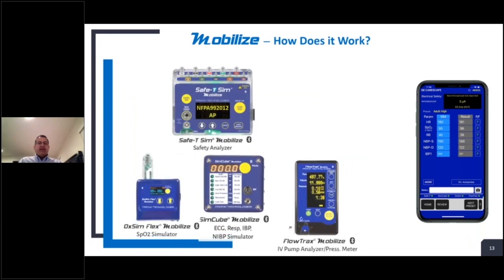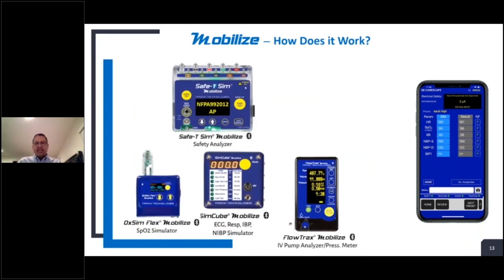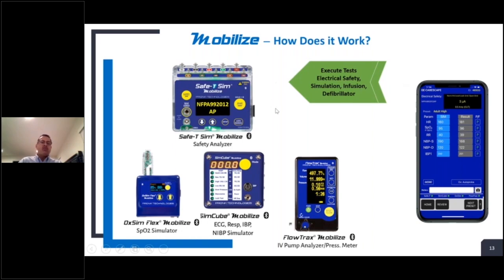So the basic idea is that you have your Mobilize test equipment products. The technician creates the required tests that have to be done via your CMS system, via the app itself, and then as the commands or the requests are coming into the Mobilize platform, those commands are pushed out to the test equipment that it applies to. These commands go out to multiple pieces of equipment if that's what is required, so that you can perform simultaneous tests. So it's not done serially, it's done in parallel. All this information gets sent saying, okay, go and perform these tests. And you could do this for electrical safety, for simulation, infusion, and also defibrillator analyzer.